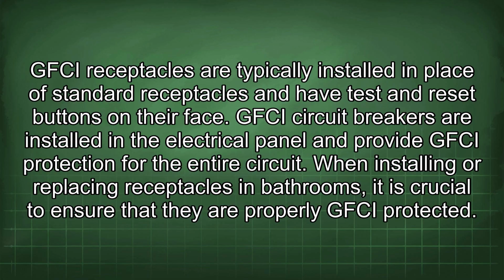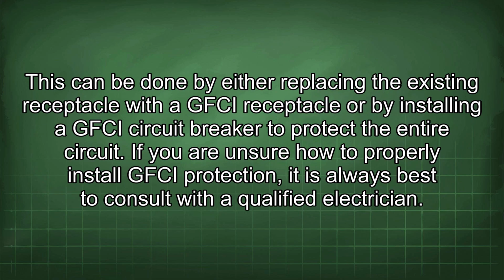When installing or replacing receptacles in bathrooms, it is crucial to ensure that they are properly GFCI protected. This can be done by either replacing the existing receptacle with a GFCI receptacle or by installing a GFCI circuit breaker to protect the entire circuit. If you are unsure how to properly install GFCI protection, it is always best to consult with a qualified electrician.